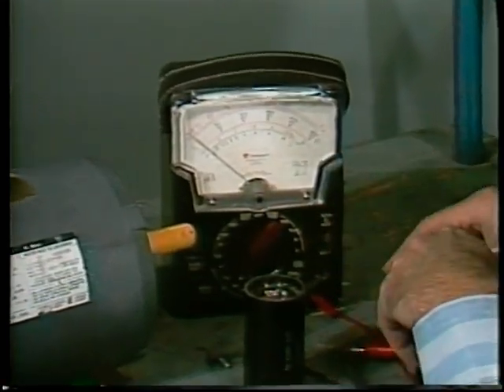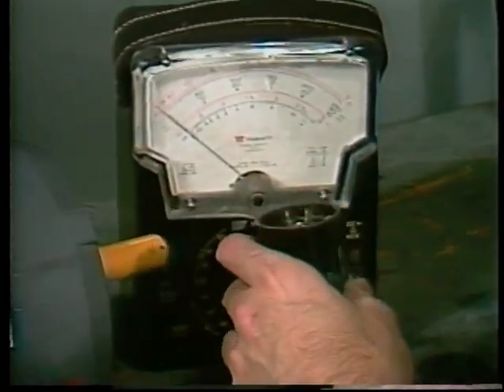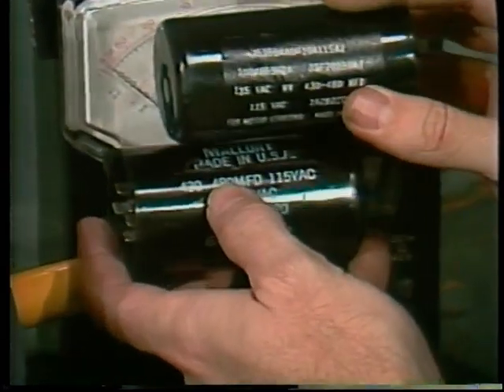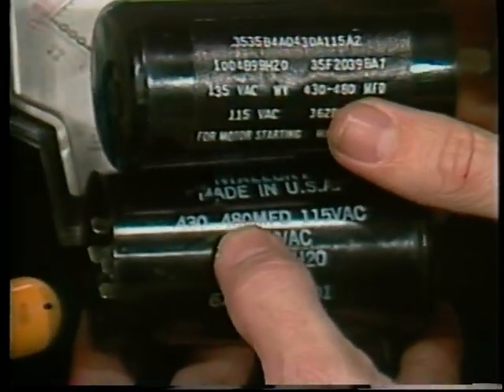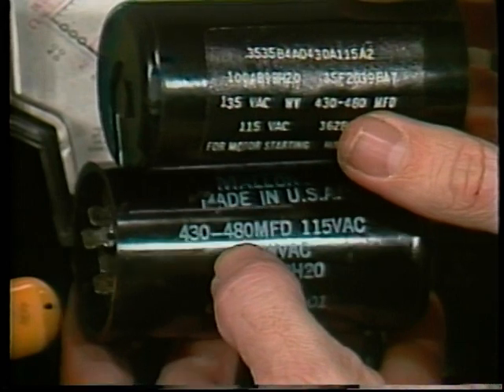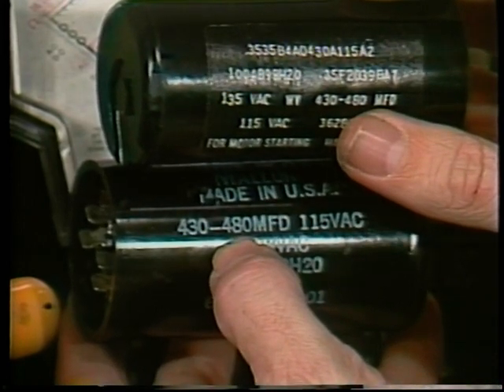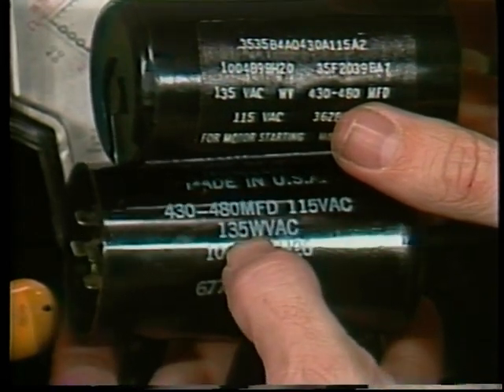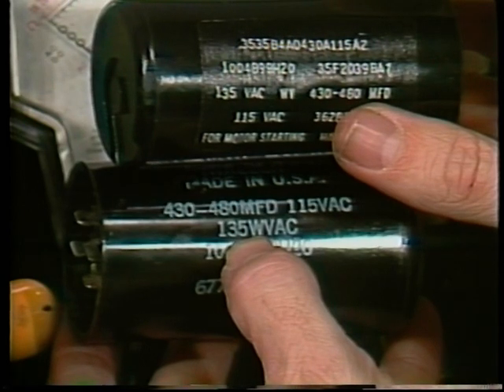Defective capacitors are easy to replace. Be sure the replacement is the same capacity in microfarads as the original and has a voltage rating at least as high. The capacitor must be able to stand a much higher voltage than the motor supply voltage.